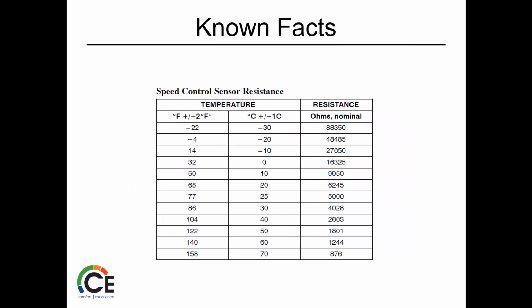So again, seen this plenty of times, right? This is the 5K chart. If anybody's been in the residential trainings, when we talk about the outdoor units, we're always talking about that 77 degrees, right? That's the sweet spot for sensors. Same thing here. If it's a 5K at 77, we should have 5,000 ohms. If it's a 10K at 77, we should have 10,000 ohms. So same basic operation, just depends on what the sensor is rated for.